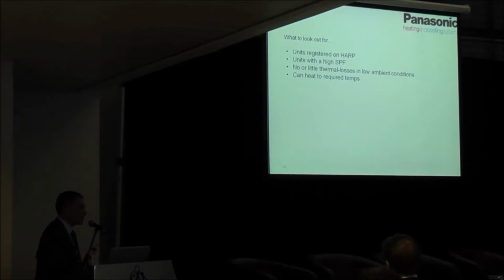So when we're designing a system, when we're looking at a system from day one, or we're looking at a retrofit, what do we need to look out for? We need to look out that the units are registered on HARP, that the seasonal performance factor is high. You need to look at your ambient conditions and look at a unit that has no or little thermal loss in low ambient conditions, and of course it can heat to the required temperatures.